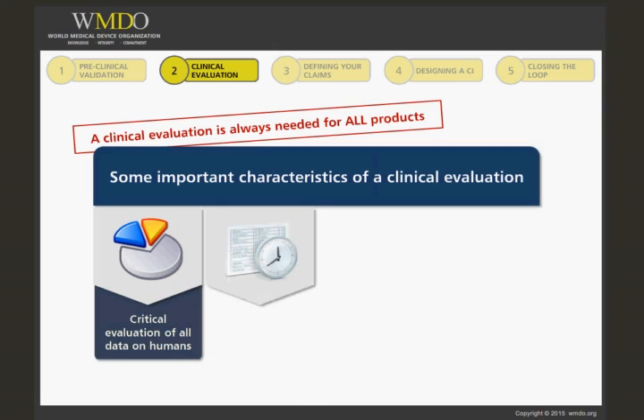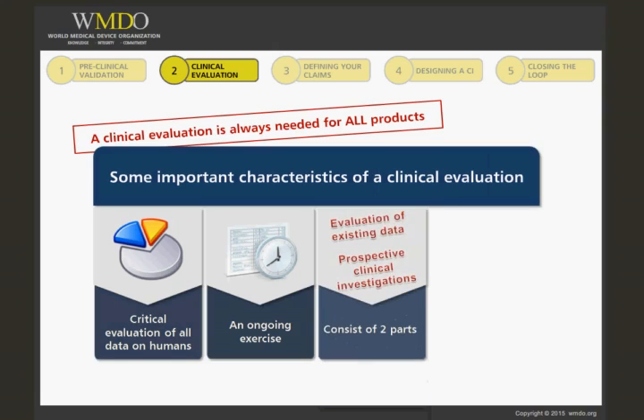Second, the clinical evaluation is an ongoing exercise which needs to be performed periodically over the lifetime a device is used on humans, whether in a clinical investigation or for commercial use. Third, a clinical evaluation consists of two parts: the evaluation of existing data and of prospective clinical investigations.